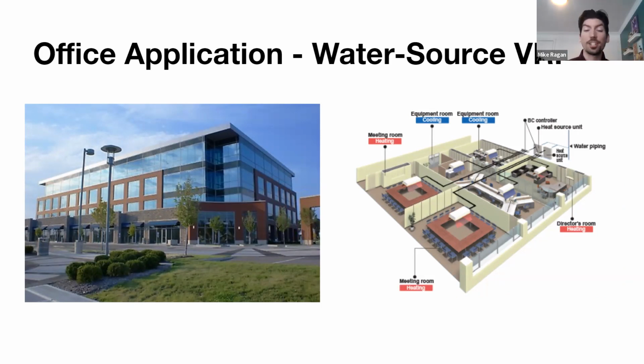And just to clarify, because I saw one question on the subject matter, if you're placing your condenser units indoors, you need to duct off the top of the condenser unit and exhaust all the heat that's being rejected from the system. And you're also going to need intake louvers in that space in order to deliver fresh air over that coil. So just as an aside, because I saw a clarifying question on that.